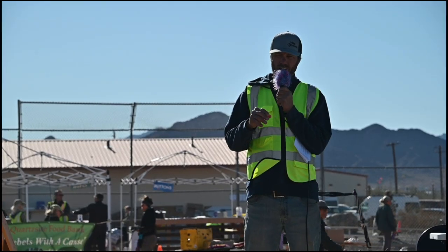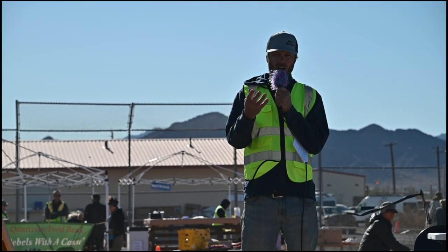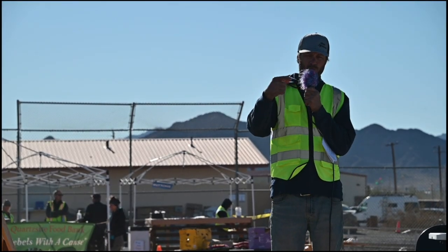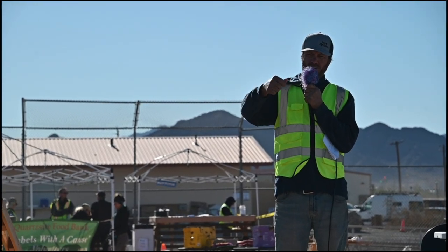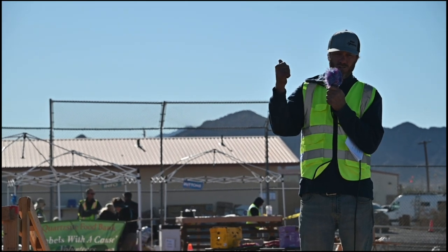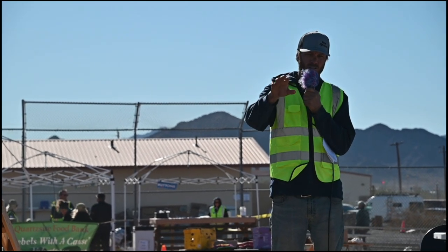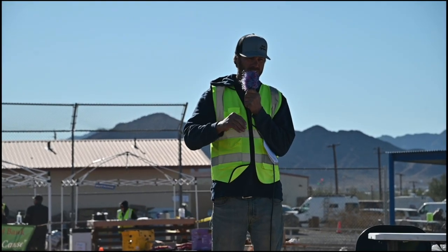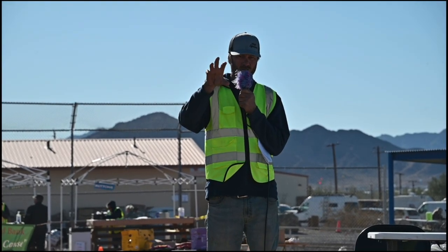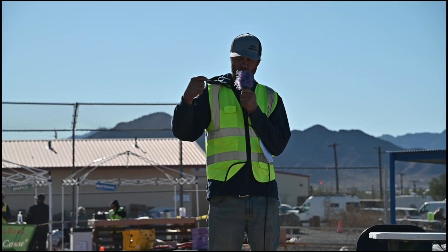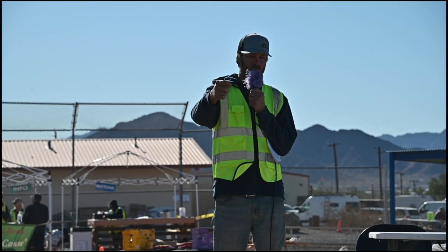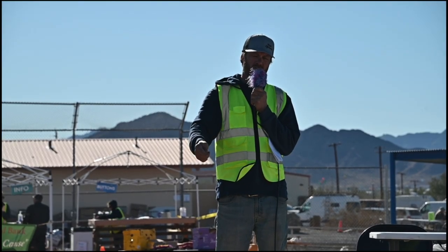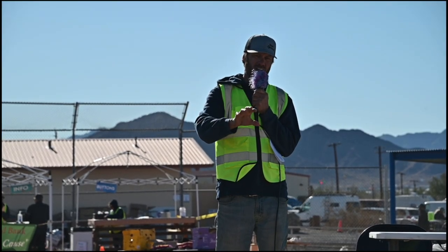Grounding is to help protect you in case something happens inside the device. Say you're dealing with a charge controller and the positive wire touches the body of the charge controller. If you touch the body, you're going to get shocked. If it's properly grounded, that body actually has a wire that attaches to it and brings it down to ground. So when that positive wire touches that body, it has a place to go, so when you touch it, you're not going to get shocked.